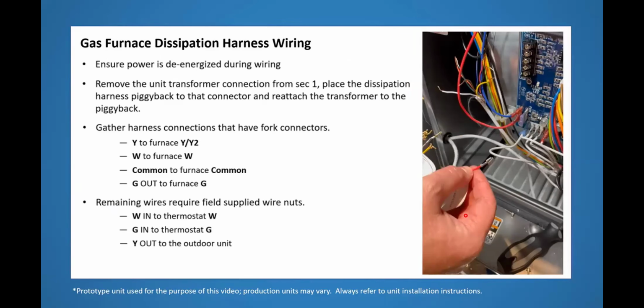Four of those wires have those C connectors on them that fit really cleanly under the thermostat strips. It's almost like a spade connector, but it's in the shape of a C, and it fits under these thermostat connections on the furnace circuit board. So four of them are going to go there. Three of the wires are bare wires with nothing on the end of them. Those are going to get wire nutted. And then one of the wires is the piggyback spade.